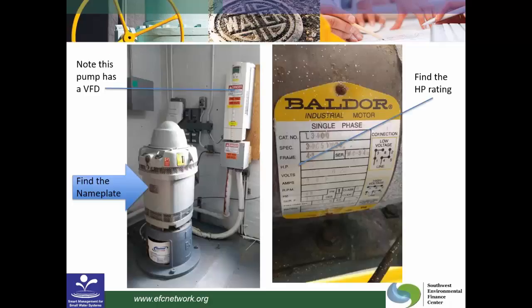So here are just a couple of examples of what you'll be looking for. So first, you want to take a picture of the overall equipment, so a big picture of the pump, the VFD on this pump, and then you want to find the nameplate. So on this particular pump, it was convenient and easy to see. On this particular pump, it was up against the wall, so I stuck my phone back behind there and snapped a picture of it. But what you're looking for specifically on this nameplate is this horsepower rating.